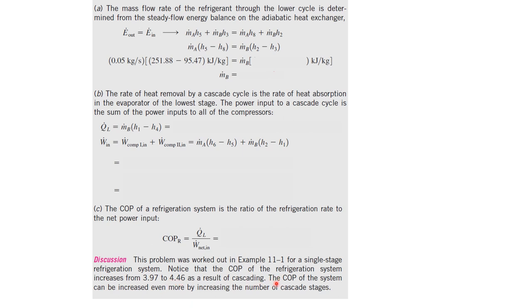This shows that the COP of the system can be increased even more by increasing the number of cascade stages. So in short, what I would like to highlight here is that a cascade refrigeration system helps improve the performance of the overall refrigeration cycle, as evident by the COP values compared to a single stage refrigeration system for the same pressure values, where the cascade system's COP is much higher.